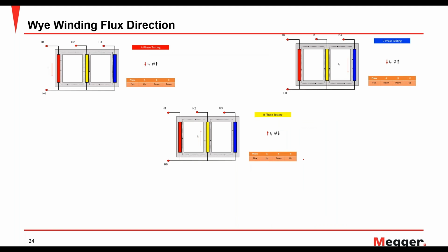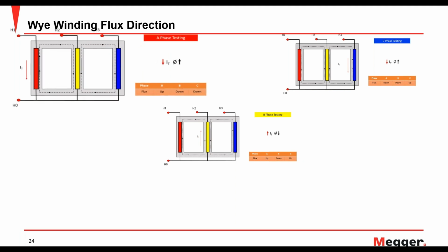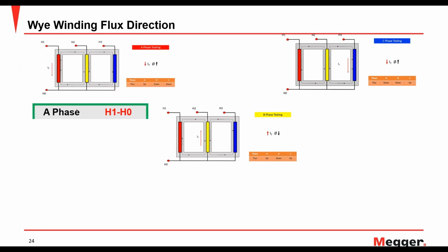The reason being, if you supply the flux opposite to whatever it was set to, it will take much more time to set up or stabilize the current in that case. For example, if you are doing A phase testing, your current is flowing from H1 to H0 and your flux is getting set up in this direction. You want to make sure that you are testing the adjacent phase to set up the flux in the same direction. Otherwise, you're working against the flux, so you have to give it more time to stabilize.